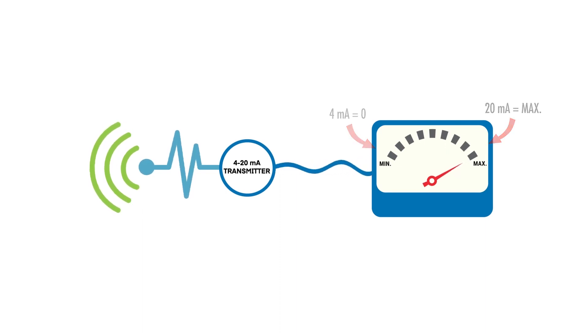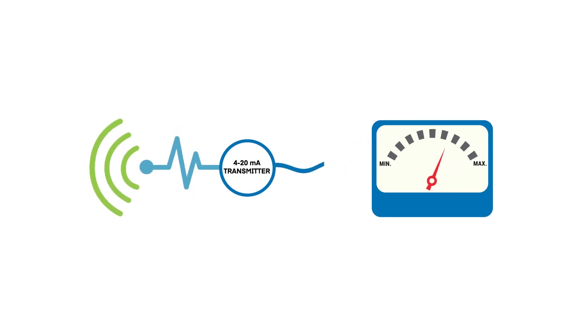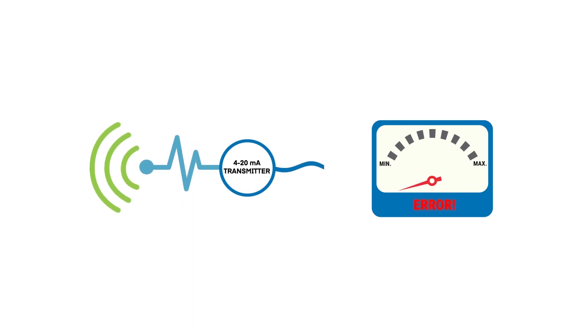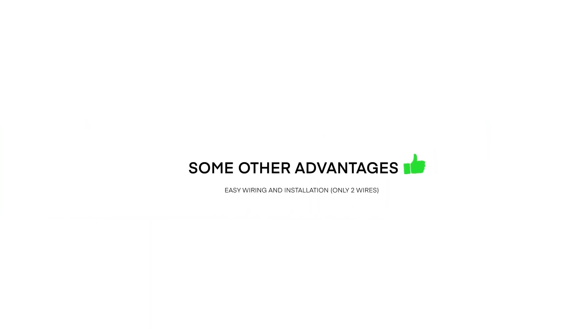This makes troubleshooting very easy, since a reading at 0 milliamps will indicate an open circuit or lost feed. Other advantages include easy wiring and installation, since only two wires are needed between the sensor and the receiver.